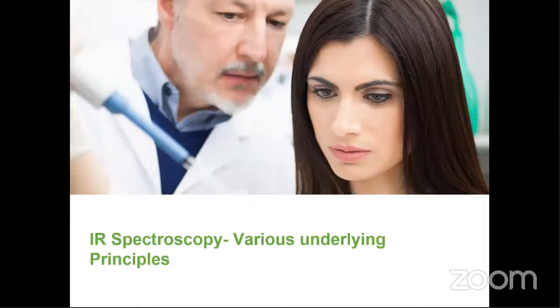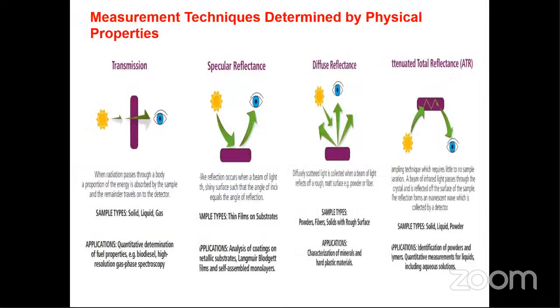So what are the various underlying principles IR spectroscopy is working with? There are four basic principles for the physical properties we are working with: transmission, specular reflectance, diffuse reflectance, and attenuated total reflectance, ATR. In transmission, radiation passes through the body and is absorbed by a sample, and the remainder travels to the detector. It's transmission.